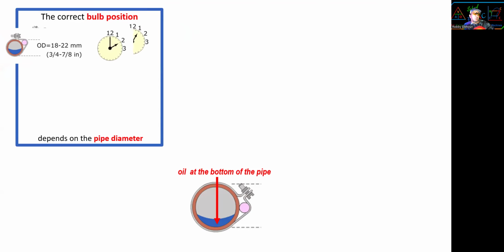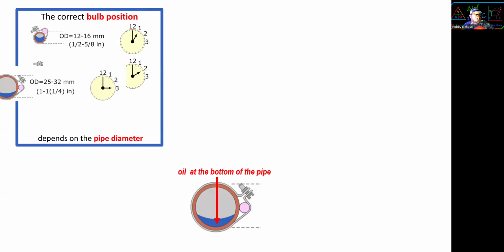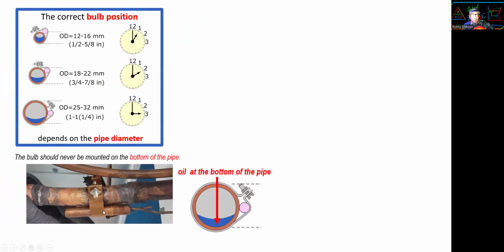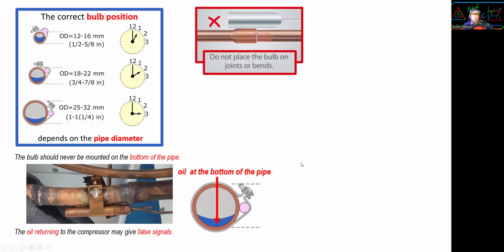Now, correct bulb position depends on the size of the pipe. Alrighty. Oil goes at the bottom and you don't want to put the bulb at the bottom like this. This is bad. It's barely contacting here because it's next to a joint connection. And look at this joint. You can tell it's hillbilly work, and it's going to leak here. Liquid line touching, very nice. Alrighty. The oil return is at the bottom. Next, do not place the bulb on the joint bend.